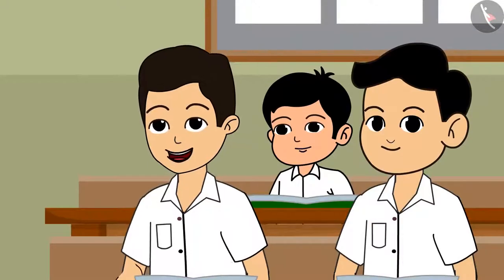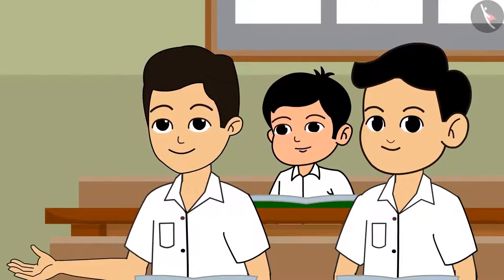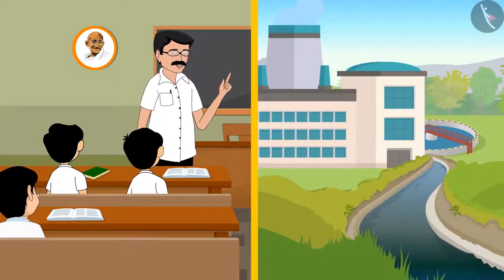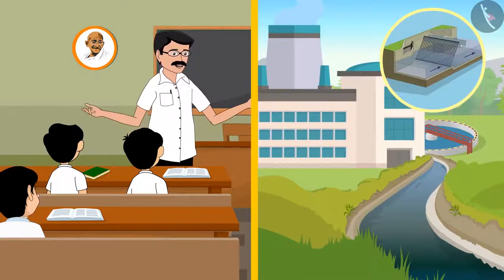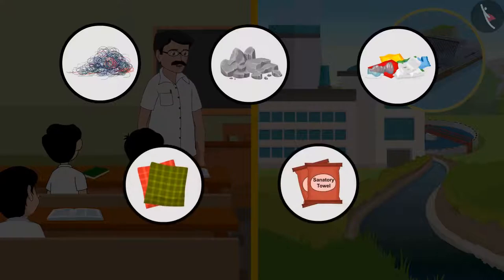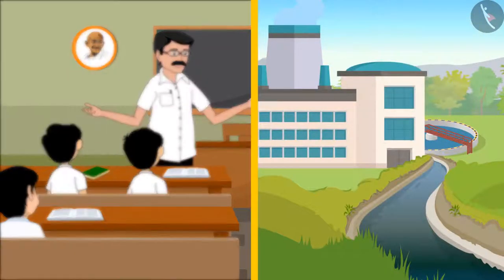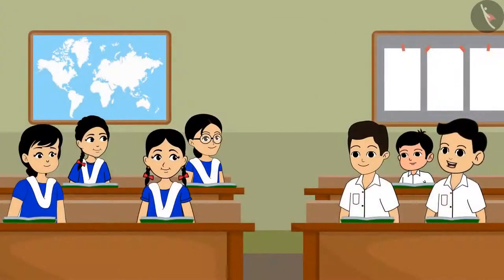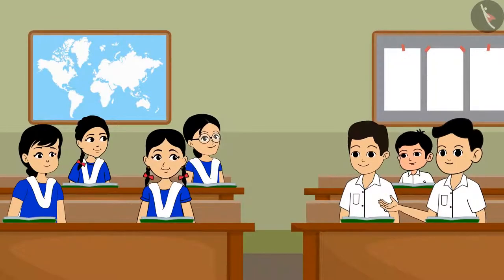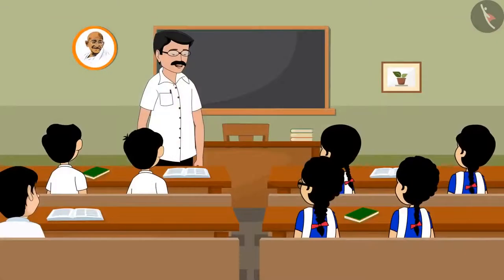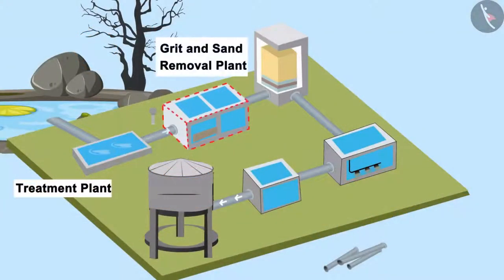Sir, can you explain the whole process of waste water treatment to us? Yes, this entire process is of 4 to 5 steps. In the first phase, sewage water is flown through the screen or mesh of the treatment plant, separating some of the larger sized suspended materials like fibres, stones, packets, napkins, etc. In this way, about 60% of the suspended particles are separated by the process of filtration. That is why we should not put all these things in water. This water is then sent to the grit and sand removal plant. Here, sand, egg peels, bone fragments, etc. are separated.